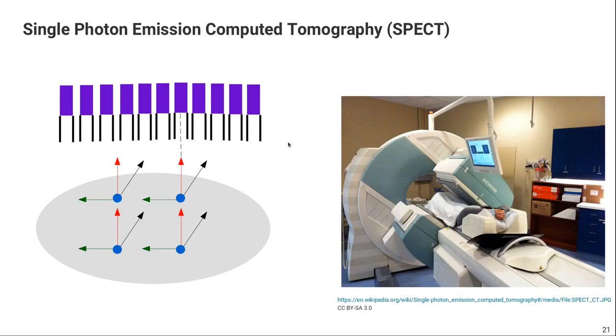And you can see an example of such a system here. This is a clinical SPECT system as you can find it in many hospitals. You can see here, this is a detector head containing many detectors and a collimator. The collimator is shown here. Keep in mind that the way I've shown it here is not really how a detector head in a SPECT system works, but for understanding the basic principle, that's enough.